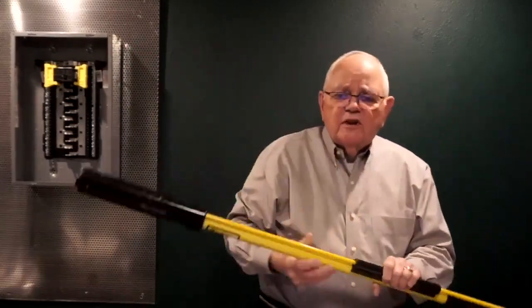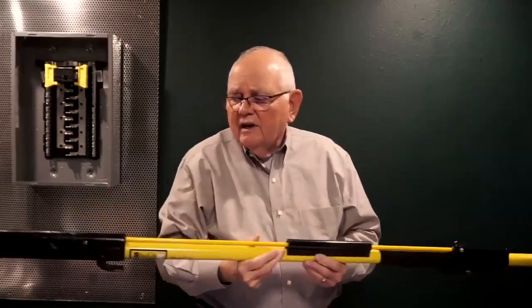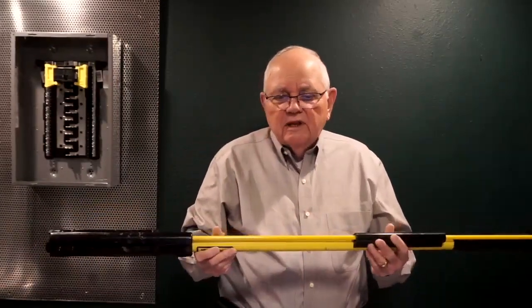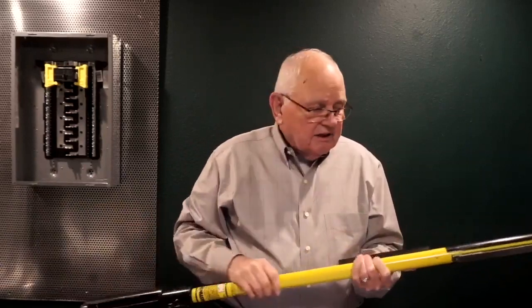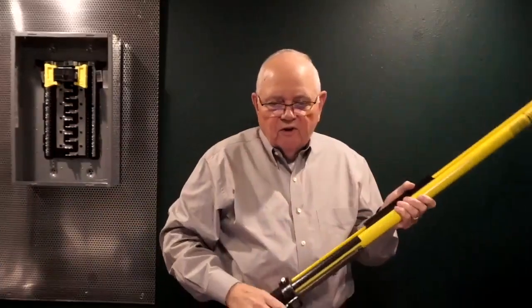Now, insulated tools. Let's talk about something else. There are 8 steps to creating this electrically safe work condition in NFPA 70E. The last step has you install temporary protective grounds. Normally, we don't do that unless we're working on some medium voltage system or above. I want to show you what we use, though. This is an example of an insulated tool, and this is a live line tool. This is called a hot stick or shotgun, often referred to.